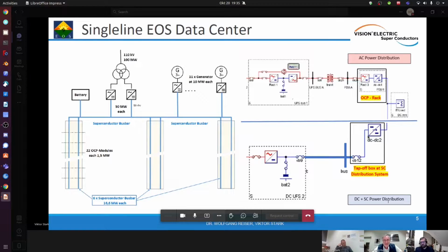So we see here there's rectification at the beginning, the direct-attached battery with native 400, 500 volts, and then direct supply through the busbar with the tap-off system we'll show in a bit, which has only DC-DC conversion down to the 48 volts of the OCP rack, correct? Correct, yeah.